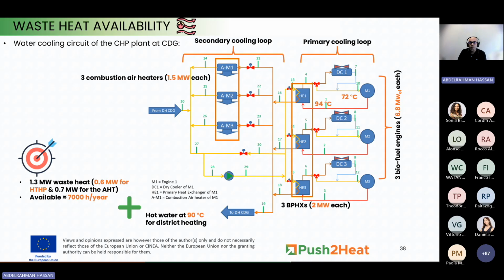a primary cooling loop, which cools 3 fuel engines of 6.8 megawatt electricity each. As you can see, the outlet water temperature is in the range of 94 degrees, and the return temperature should be in the range of 72 degrees. This heat is rejected to a secondary cooling loop through these 3 brazed plate heat exchangers. Each one has 2 megawatt capacity.